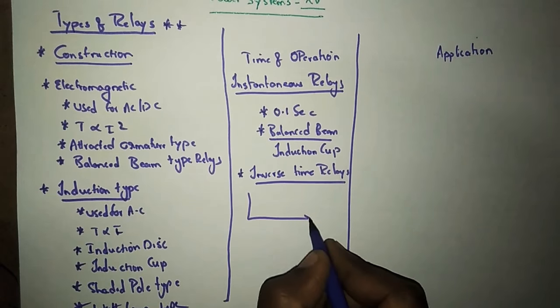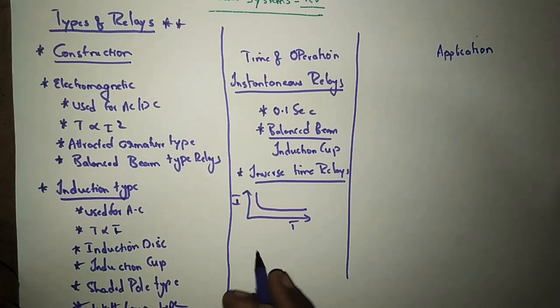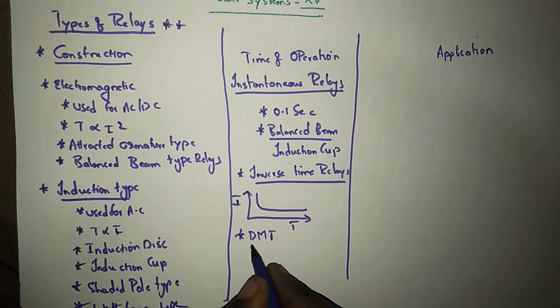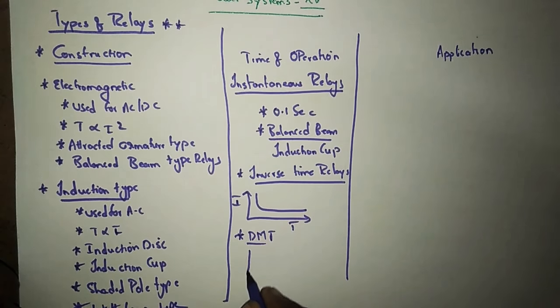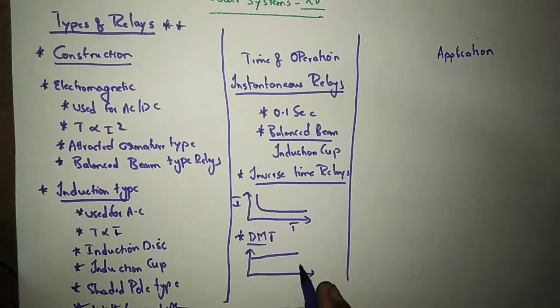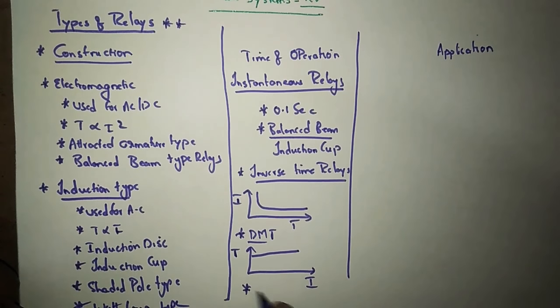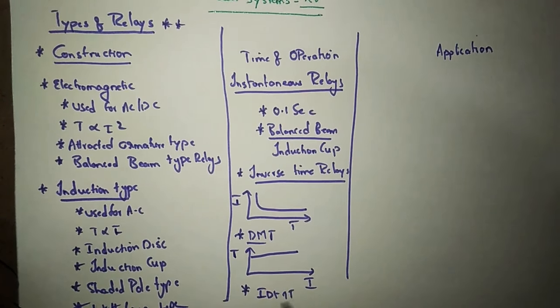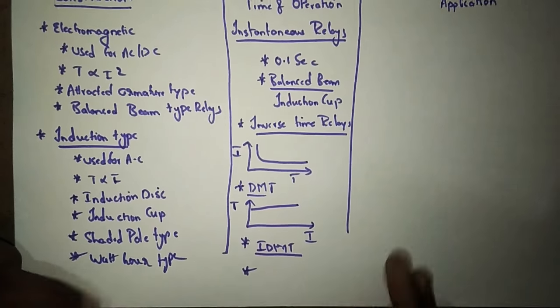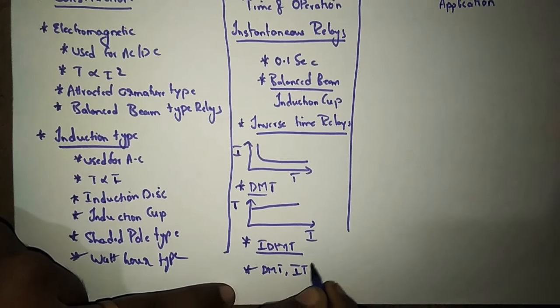Next comes inverse time relays. Inverse time relays are those where current and time are inversely proportional. Next comes DMT — definite minimum time interval — where for any magnitude of fault current, the operation time is constant. After that comes IDMT relays — inverse definite minimum time relays — which are a combination of definite minimum time relays and inverse time relays.